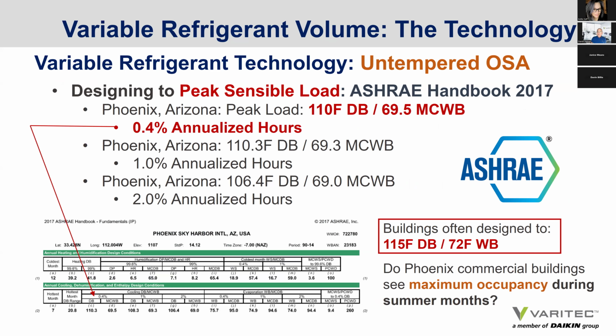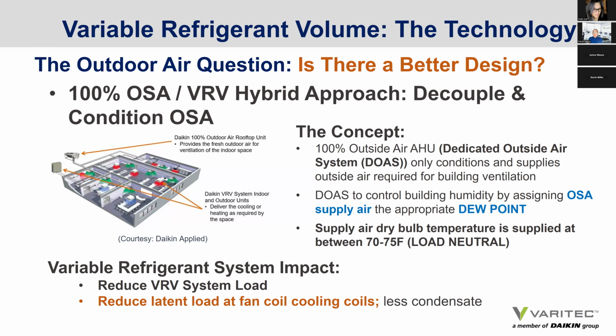So another problem is that if you design the variable refrigerant system with untempered outside air, you're designing to your peak summer design condition. Well, for Phoenix, Arizona, we see 110 degrees only 0.4% of our annualized hours. Oh, and by the way, we see 115 degrees, and we're topping out at 120. So it begs the question of whether we're oversizing the mechanical system to handle these peak design conditions, which means the variable refrigerant system is not offering its efficiency at part load conditions. So is there a better way to design variable refrigerant systems? And by the way, again, Peter Rumsey suggests that there is.